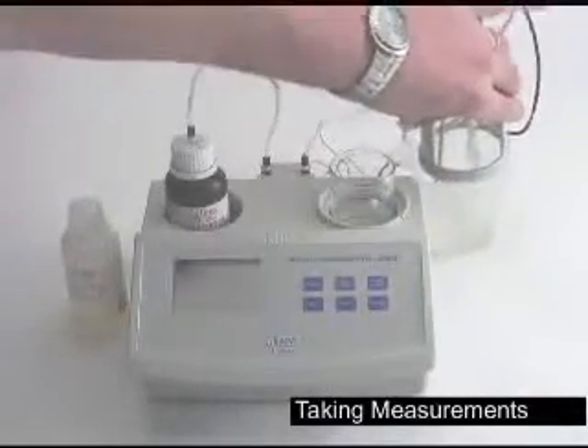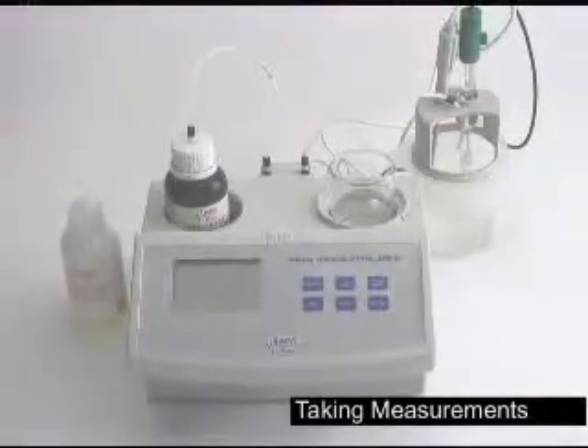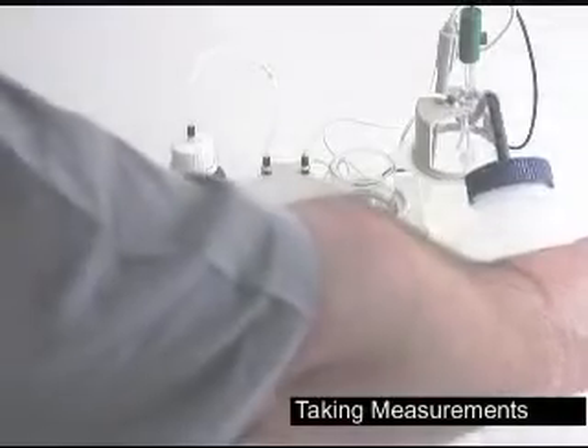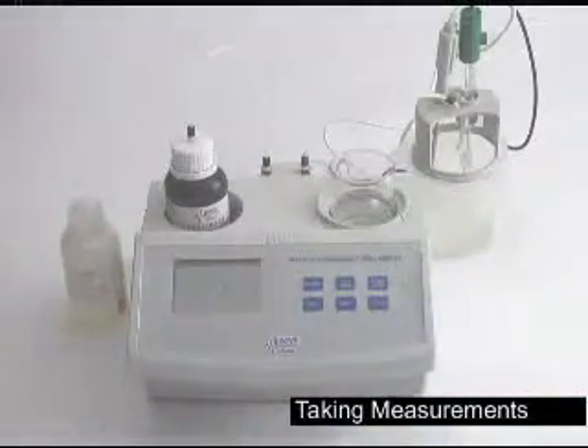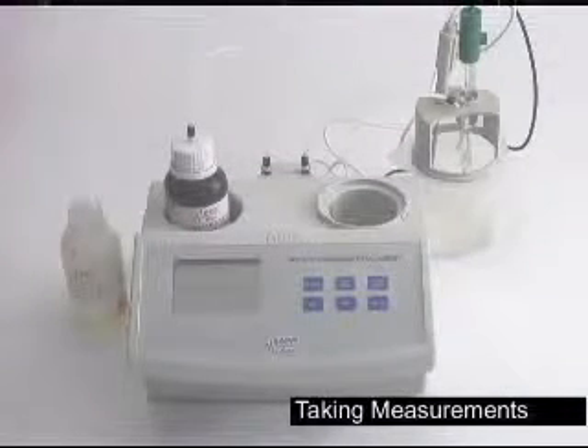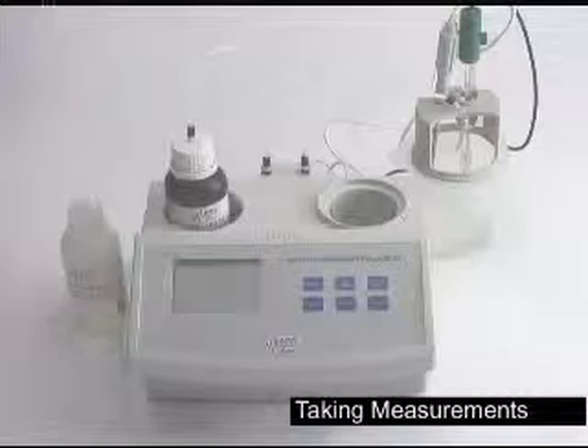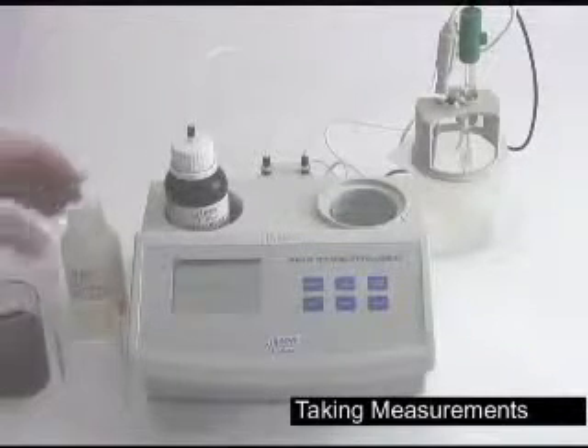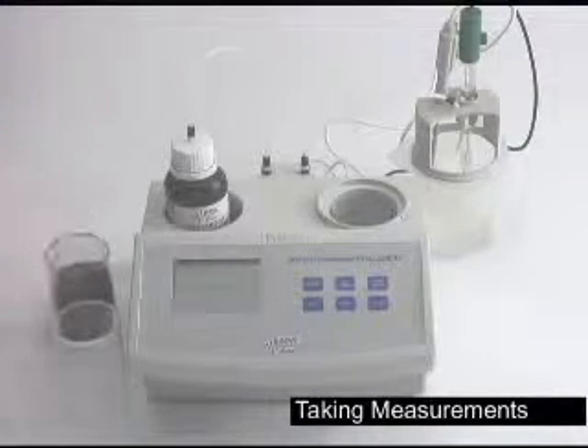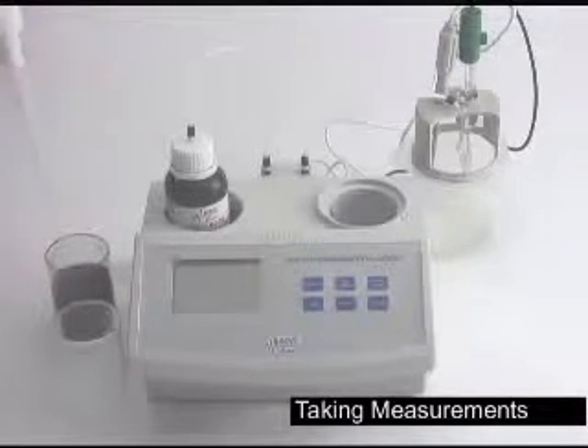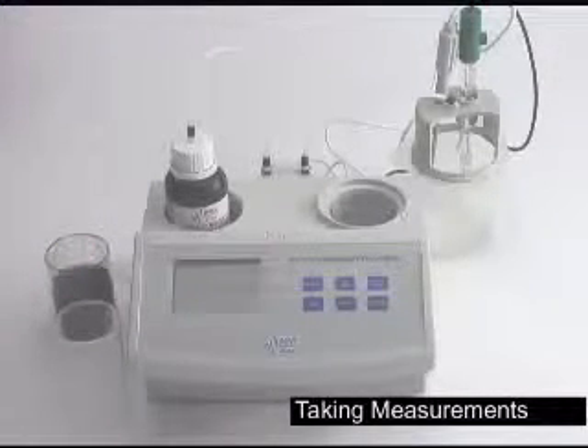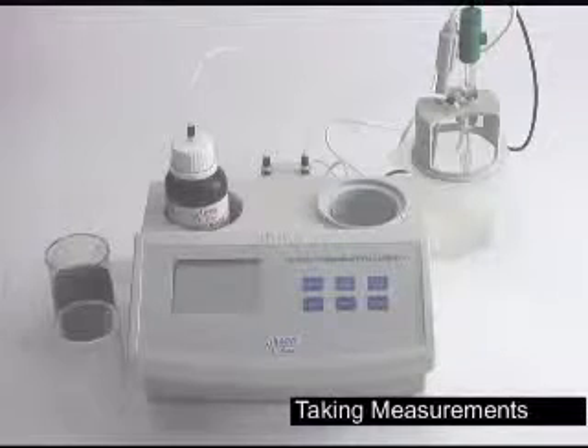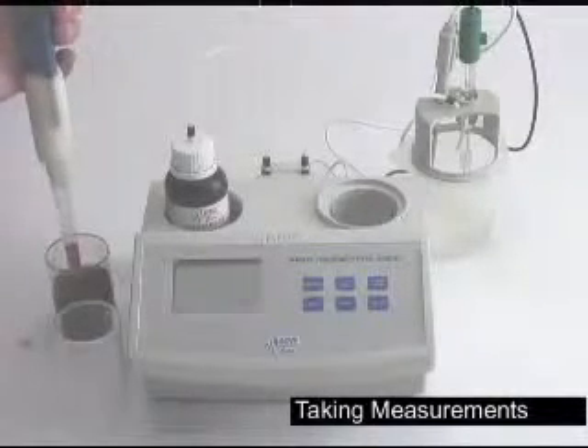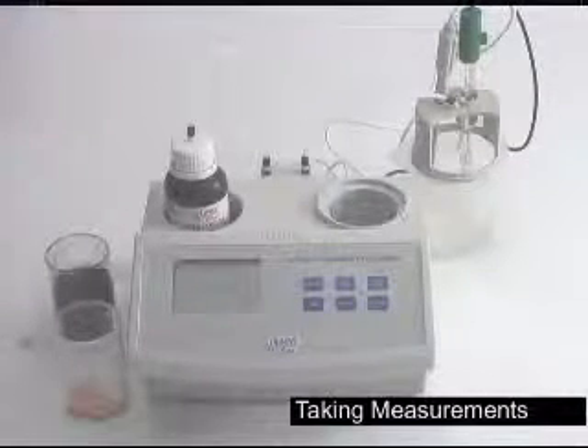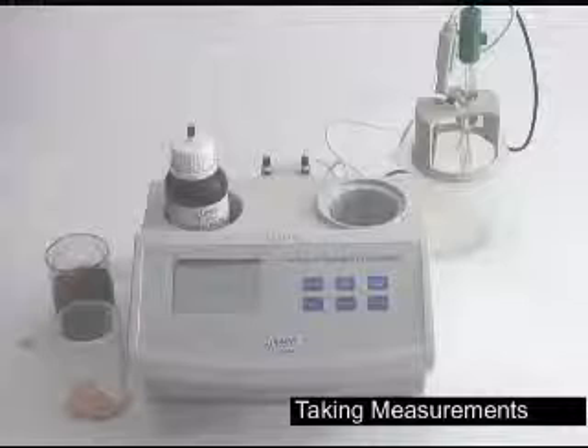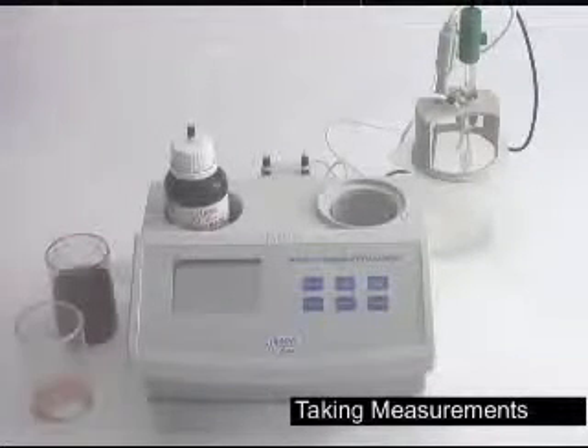Remove your cap. Always rinsing your probes in between each test. Again, take a clean beaker and some wine to be tested. Same as using the standard, we're going to take 2 milliliters of the wine. First I'm going to rinse the pipette to make sure it's clean. Pull your 2 milliliters, place it in your beaker, same way we did the calibration. We're also going to bring it up to volume with deionized water, bringing it to the 50 milliliter line.